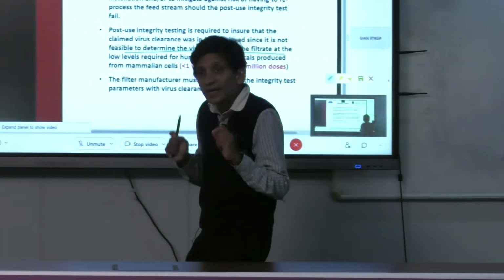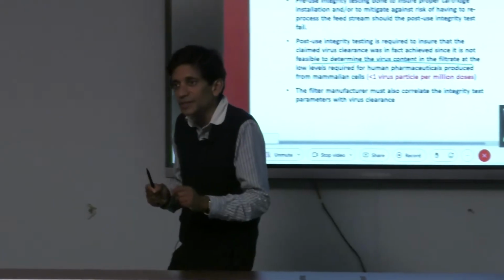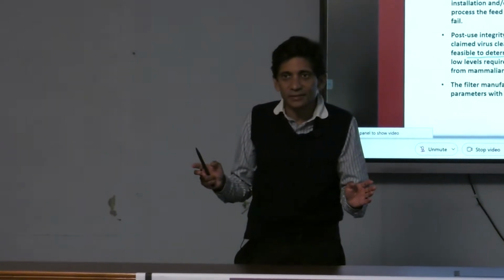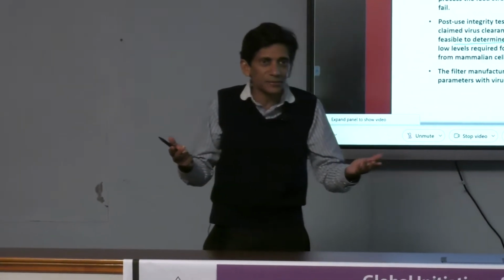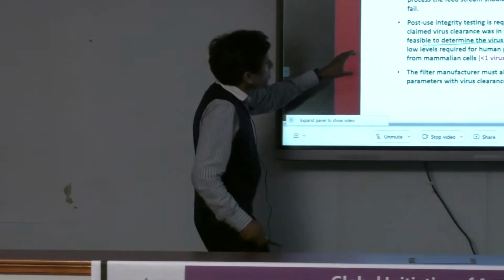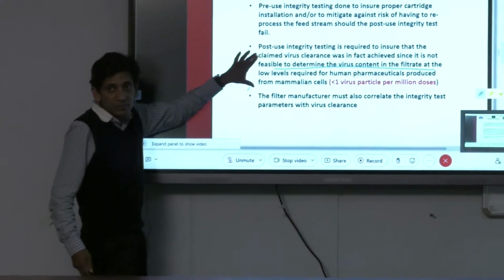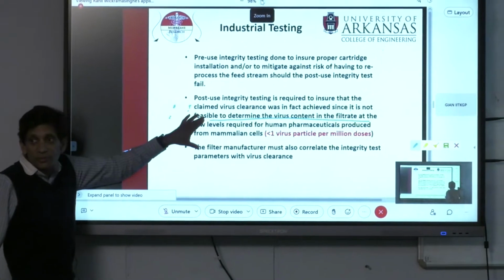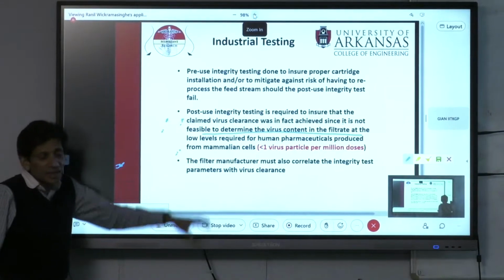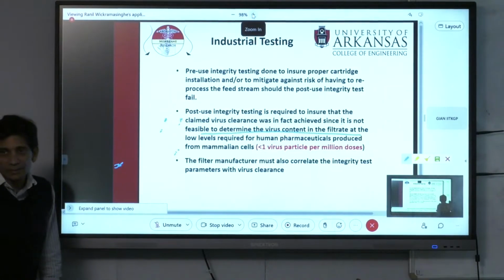These are all destructive tests, which means once you do the test, you can't use the filter again, okay? But that's fine, you're going to throw it away anyway. But this is a very important part, because if you fail this test, which could happen, you've lost your product or you're going to reprocess it. And reprocessing is not easy, okay?